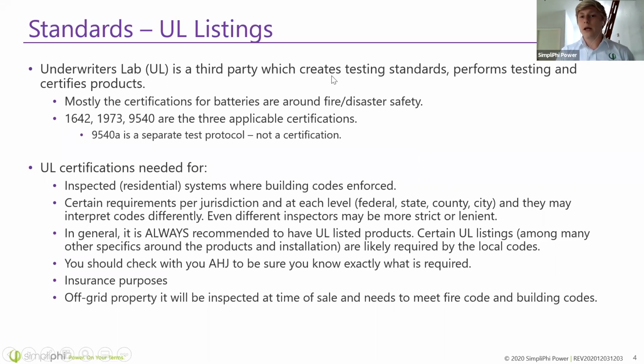UL is a third party that creates testing standards. They perform tests and they certify products as safe. These certifications are mostly based around fire safety and disaster safety. Three applicable certifications for batteries are 1642, which is cell level, 1973, which is module level, and 9540, which is a system level certification, making sure that all the components in the system are able to safely work together.